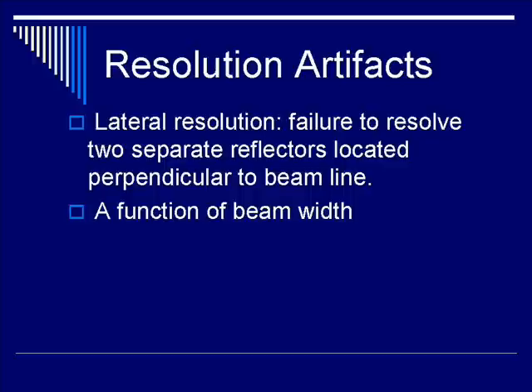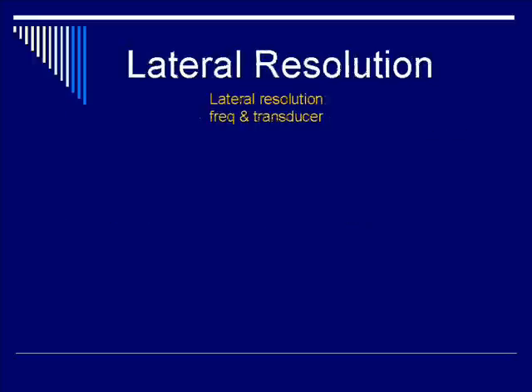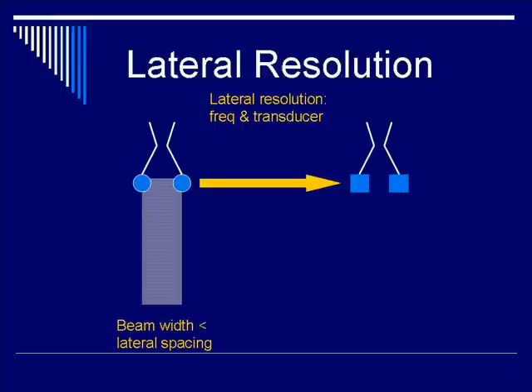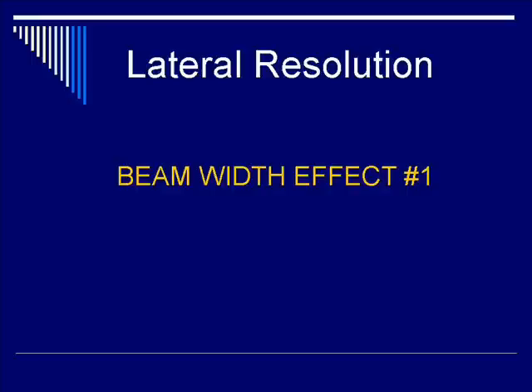Let's go on and talk about lateral resolution. By definition, lateral resolution is defined as the failure to resolve two separate reflectors located perpendicular to the beam line. Aside from being a function of frequency, lateral resolution is also a function of beam width or transducer design. Taking two point reflectors located laterally to each other, if the beam width is less than the lateral spacing of the two objects, you will be able to resolve the two objects — there will be two pixels separated by lateral distance.